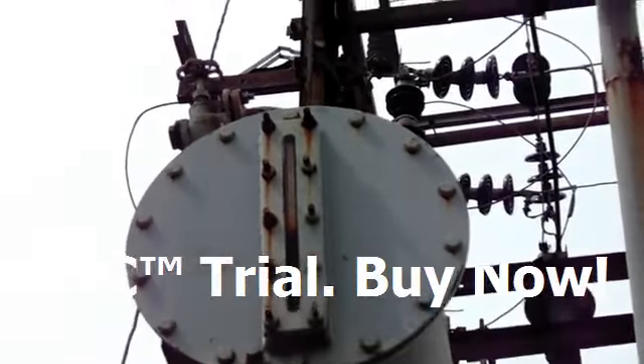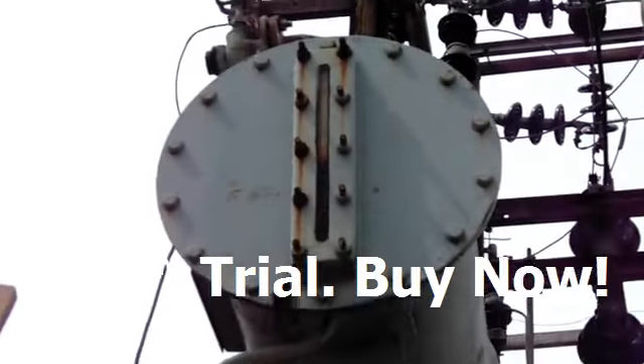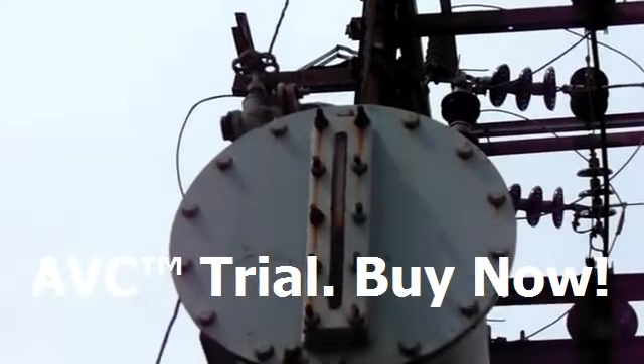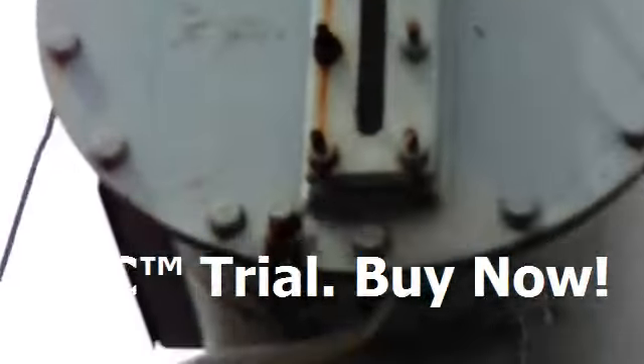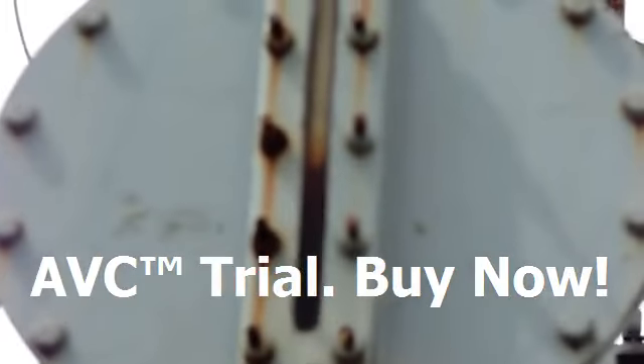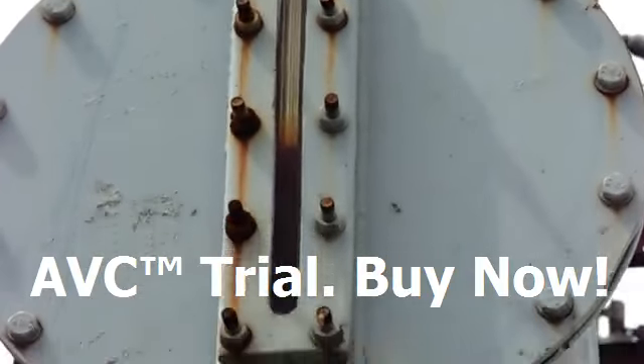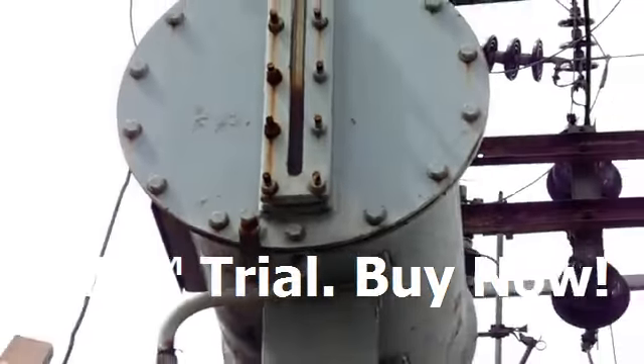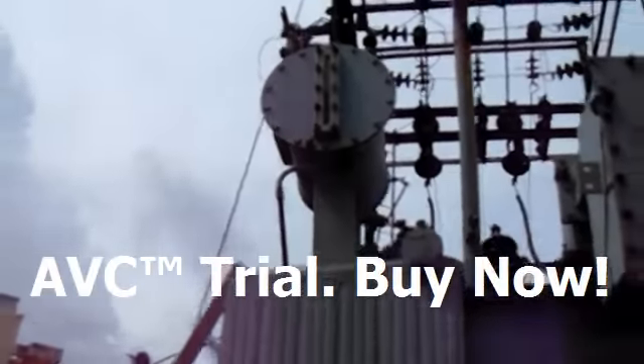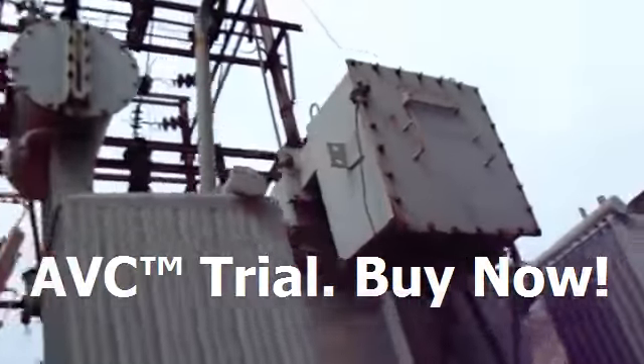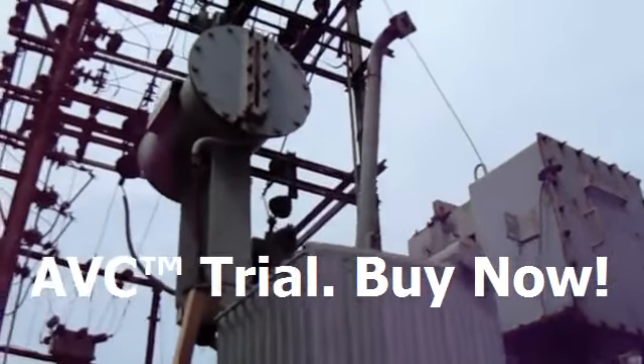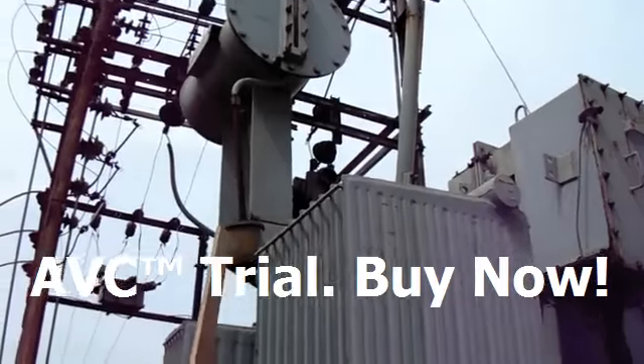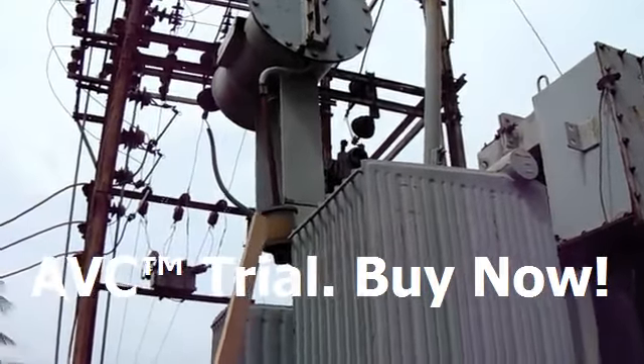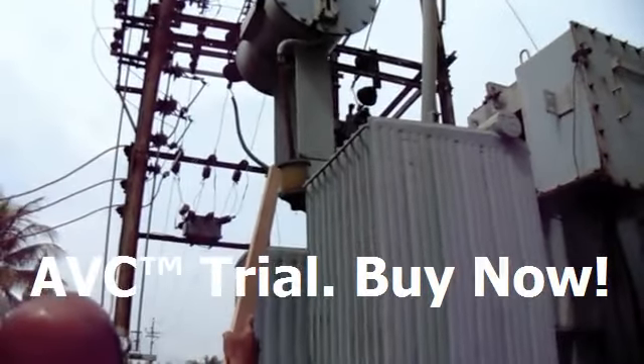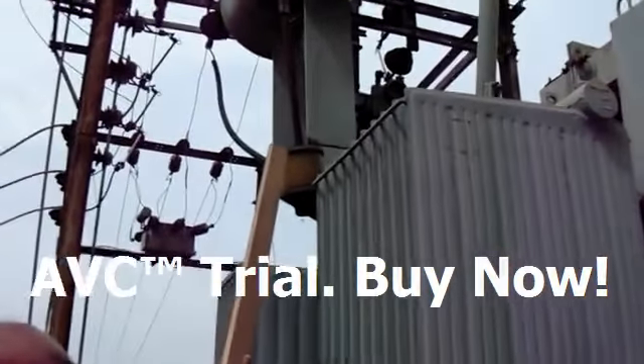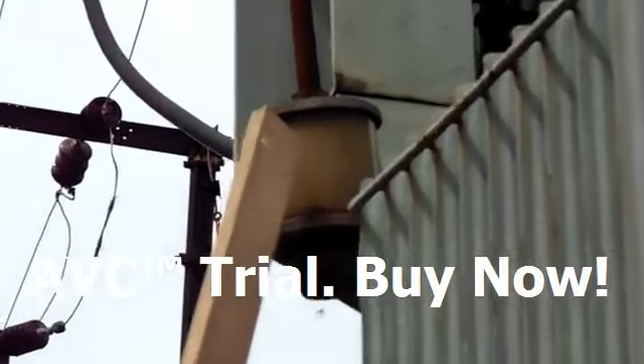So as an electrical engineer, during the summer season you should come and check the level of oil in the conservator tank, and if it comes down, you have to take the necessary action. You have to take this transformer for maintenance. You can see that the conservator tank is connected through a small pipe, a GI pipe, to another device. This is known as the breather. What is the function of the breather? The function of the breather is just like our nose, the human being's nose, to breathe in and breathe out.